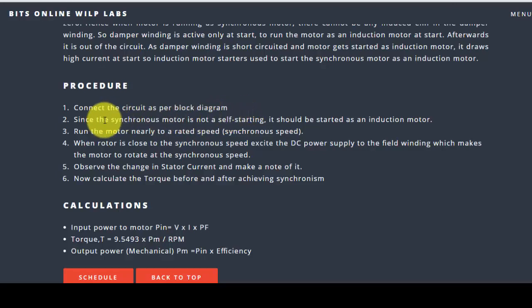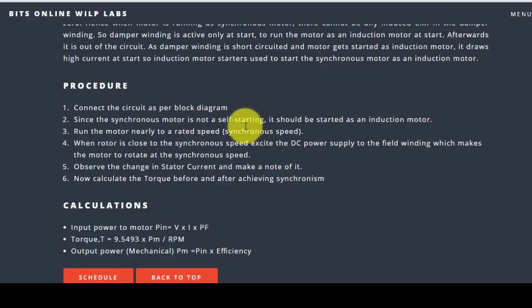Since the synchronous motor is not self-starting, it should be started with an induction motor. Firstly, we need to run the induction motor at the rated speed. When the rotor is close to the synchronous speed, then we can excite the DC supply to the field winding which makes the motor rotate at synchronous speed. We can observe the change in the stator current and make a note of it.